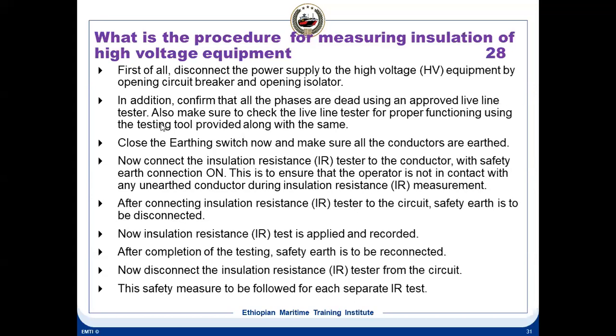You must have a line tester. It's a special probe, not a normal line tester. It's a probe about 1.5 meters long, approximately more than 1 meter. The probe is there to give a safe distance of about 1 meter. With this probe, you have to ensure that there is no residual voltage left on the conducting part. So make sure to check the live tester for proper functioning using the test tool provided along with it. So first you have to check that the probe itself is working. So you check the probe is working. With the probe, you check the live parts, make sure there is no voltage on them.